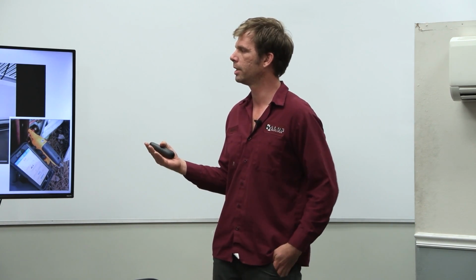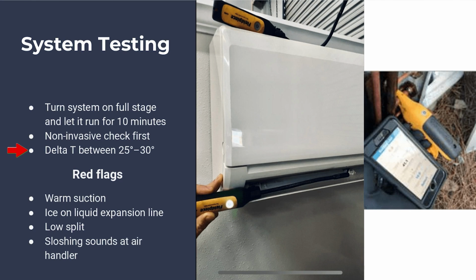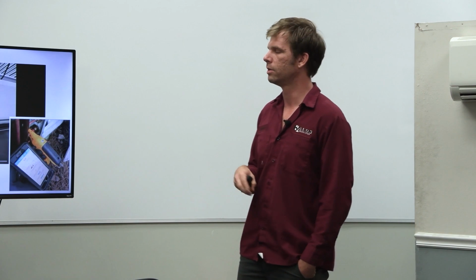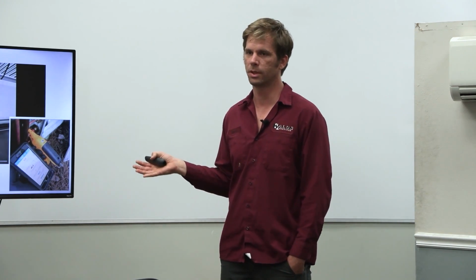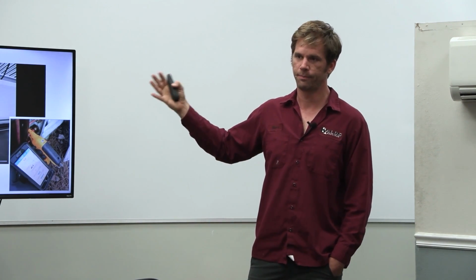The easiest and simplest way, what I use on a maintenance to know if your ductless system is working, is to take a temperature split - you're typically going to be between 25 and 30 degrees, almost always around 28. It's a pretty consistent temperature split with normal temperatures inside the space, though that can differ if the unit's been off and it's really humid and hot. On a regular AC system, our target is 20 - that's the rule of thumb you always hear.